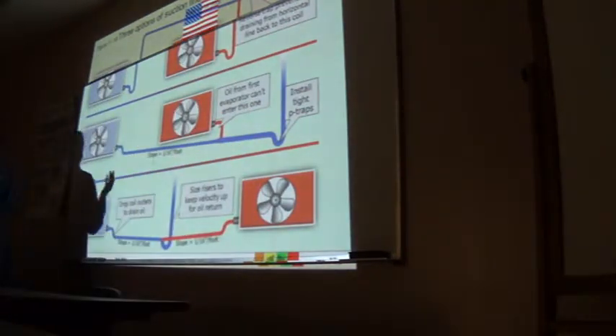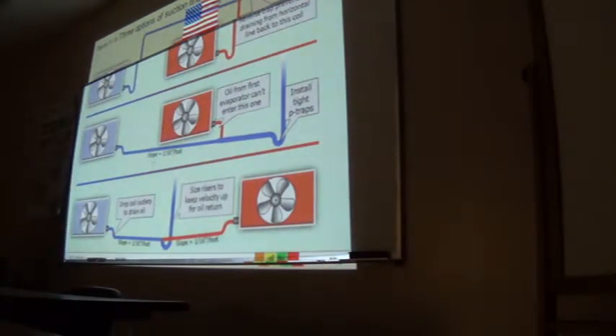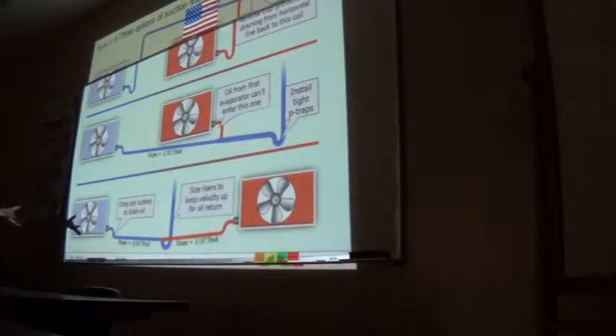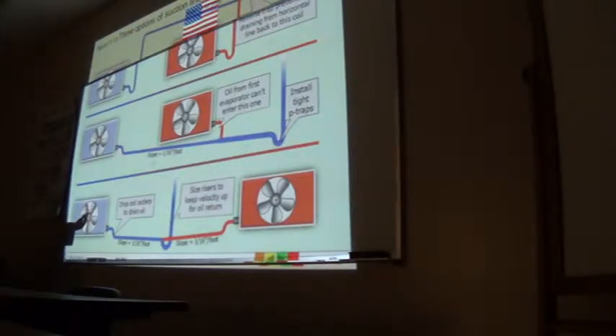And then you put a P-trap on your riser? Yes. The thing is, if you put the P-trap there, you really don't run into any kind of oil return issues. And I mean, for the past 40 years I've been doing this, I never had an issue like that, doing it that way. That P-trap only goes there if the compressor is above? Yes, only if the compressor is above.